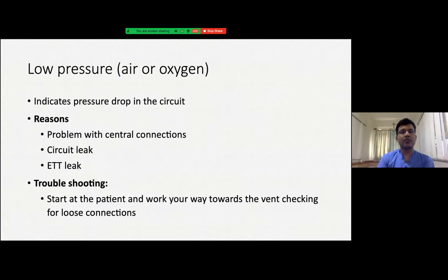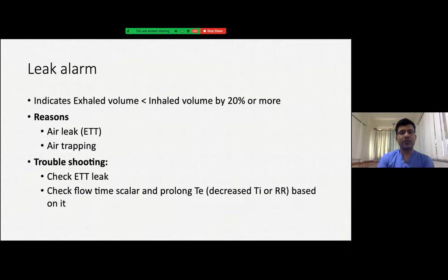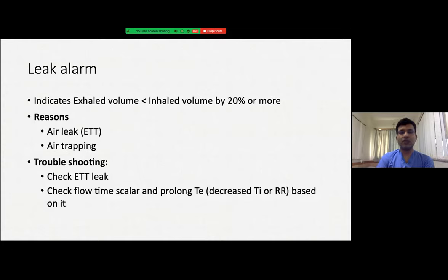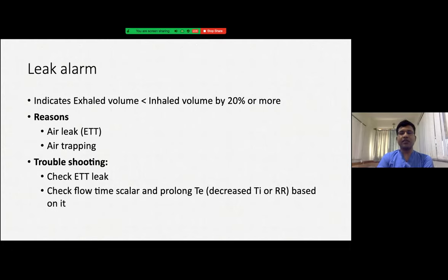A low pressure alarm occurs because of pressure drop — most commonly due to circuit leak or endotracheal tube leak, though it can also occur because of a problem with the central connections. For troubleshooting, start at the patient end and track the ventilatory circuit to the ventilator to find any leak. A leak alarm occurs when exhaled volume in the expiratory limb is less than inhaled volume by 20% or more. Reasons include air trapping or ET tube leak. Troubleshoot by checking ET tube leak and the adequacy of TE; if TE is inadequate there will be air trapping, which can be seen in the flow time scalar.